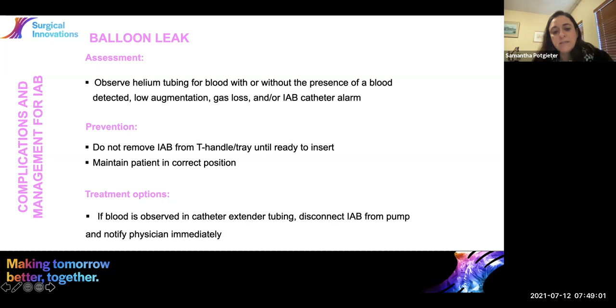So those flecks and those observations of your line and of your catheter are extremely important that you do check along with all of your observations often. And if you do observe that, the pump immediately goes into standby, and the balloon should be deflated. When it goes into standby, it does that automatically, and that catheter needs to come out.